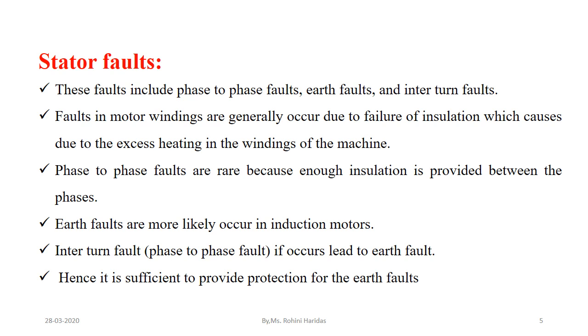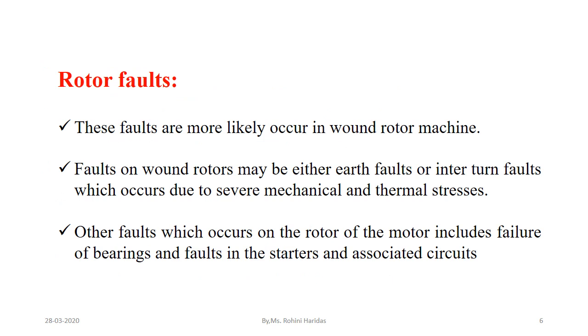Phase-to-phase faults are rare because enough insulation is provided between phases. Earth faults are more likely to occur in the induction motor. Interturn faults, if they occur, lead to earth faults; hence it is sufficient to provide protection against earth faults. An interturn fault means a fault occurring between two or more turns within a single phase winding. Rotor faults are more likely to occur in wound rotor machines, caused by severe mechanical and thermal stresses, and may include bearing failures.